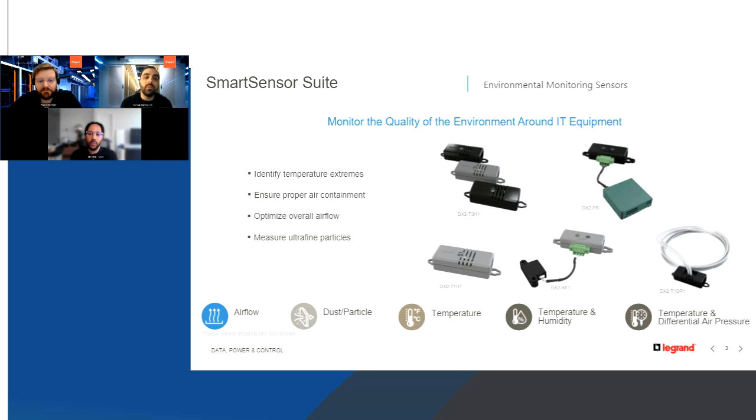The other method, if you're not using Raritan or ServerTech, is to buy a sensor module. So we have these standalone units that can be deployed within an entire row and hold up to 200 sensors off that single unit. That way, everything is aggregated into one location, and you have one connection to your building control systems, BMSs, I think, building monitoring systems. And that system would basically allow you to generate graphs and reports and provide warnings when these sensors are above a certain threshold, for example. And that could be all set from the back-end UI of either of those methods.